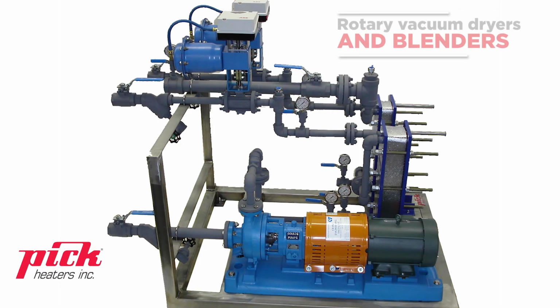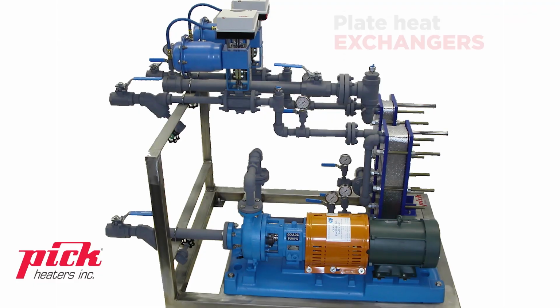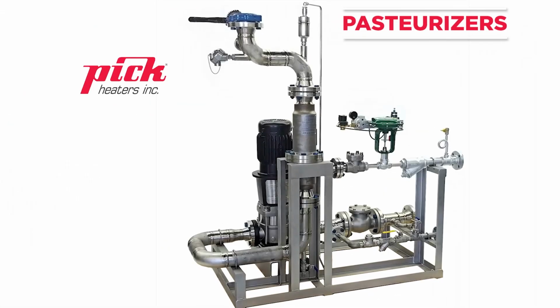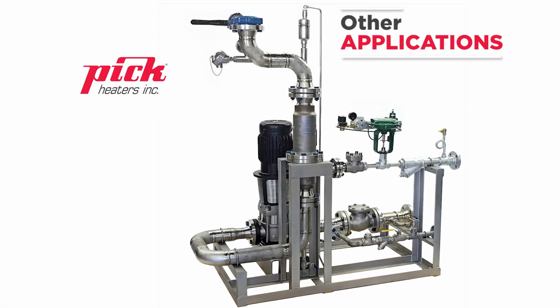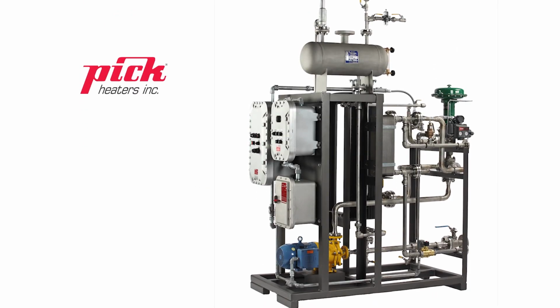With elevated steam temperature, shortened gasket life can result. As a rule, for every 10 degrees Fahrenheit above 300 degrees Fahrenheit, gasket life will be cut in half. We know that gaskets can be expensive and not readily available wherever the customer may be.